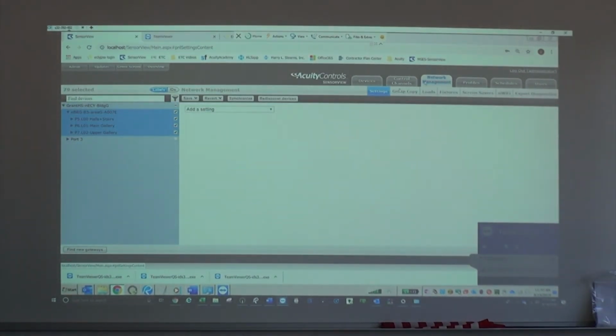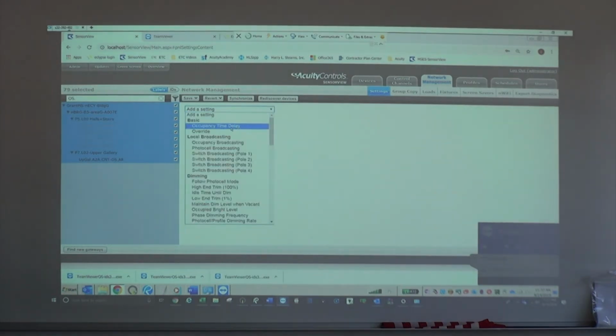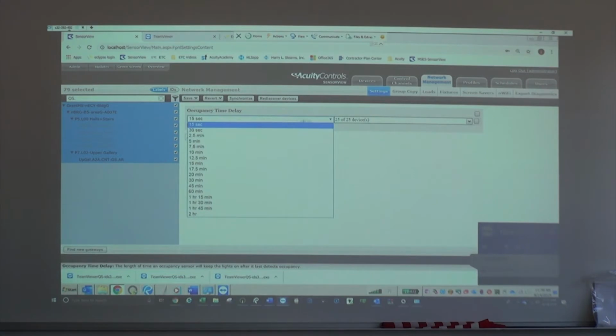We have a standard labeling scheme for all our devices. So if you type in OS dot and pull down, these are all the occupancy sensors in the building. You can select all the occupancy sensors, then select your occupancy time delay, and change everything in the building to 30 minutes rather than 10 minutes.